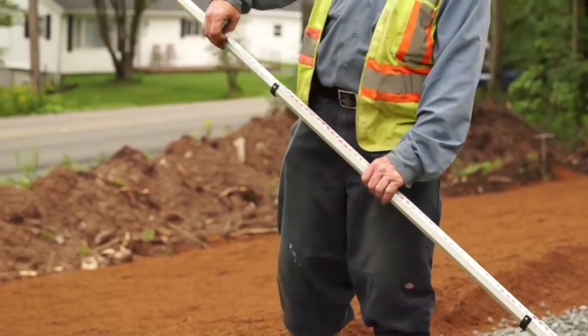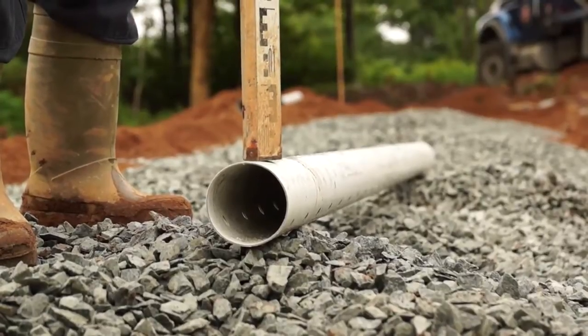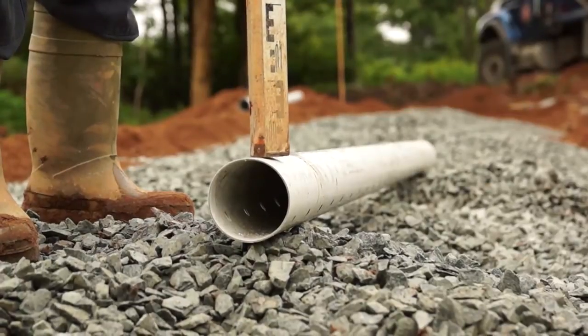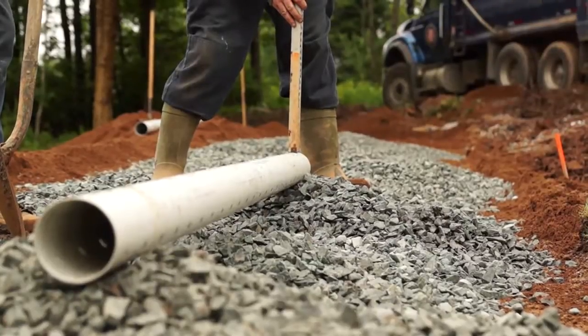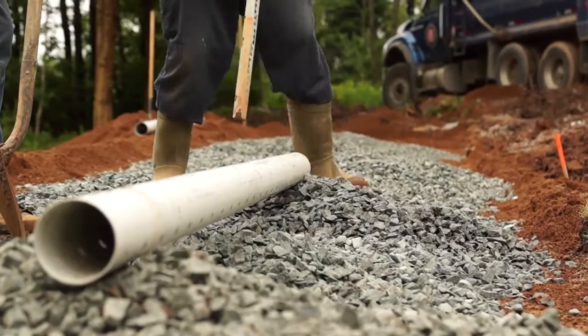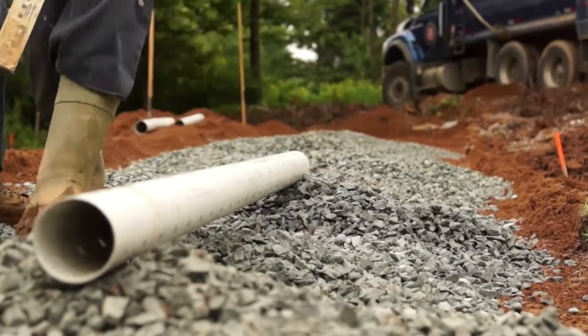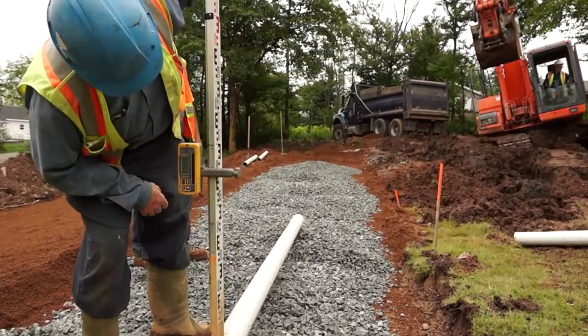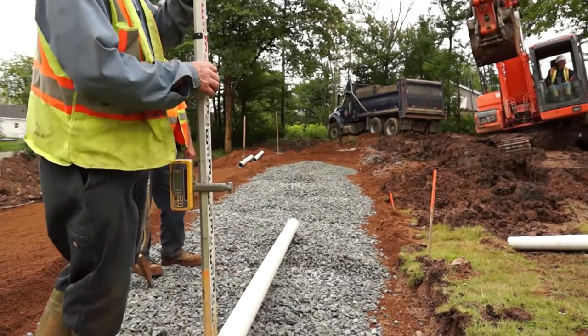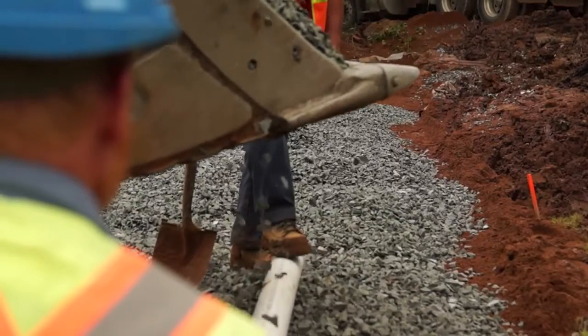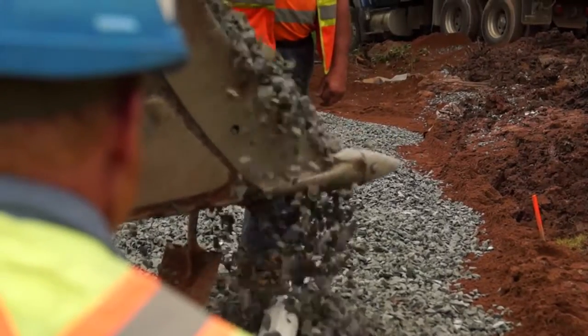In a gravity-fed system, perforated pipe is assembled on top of the stone to the proper length and slope, 1/3 of the width of the trench from the back of the trench. The pipe is covered with 75 mm clean stone.